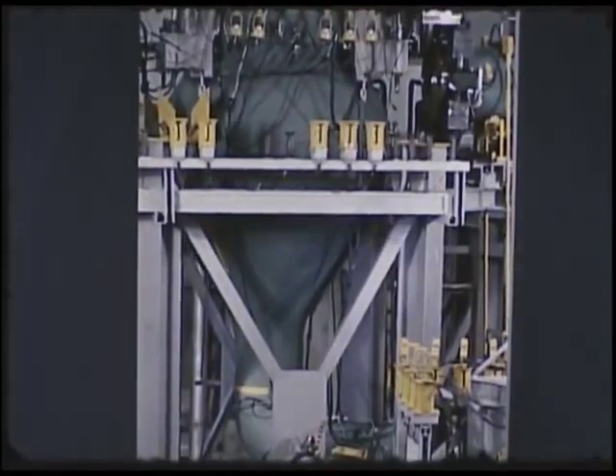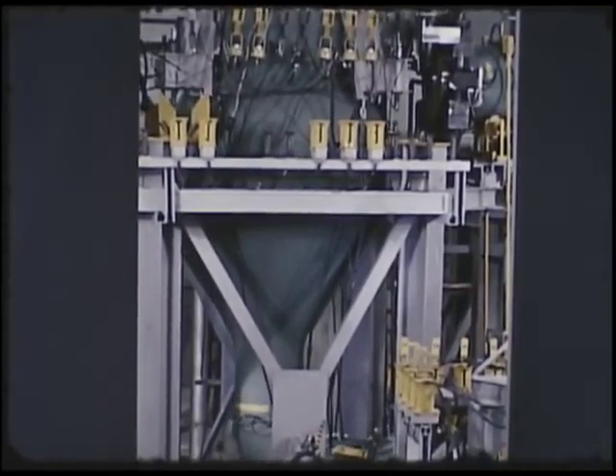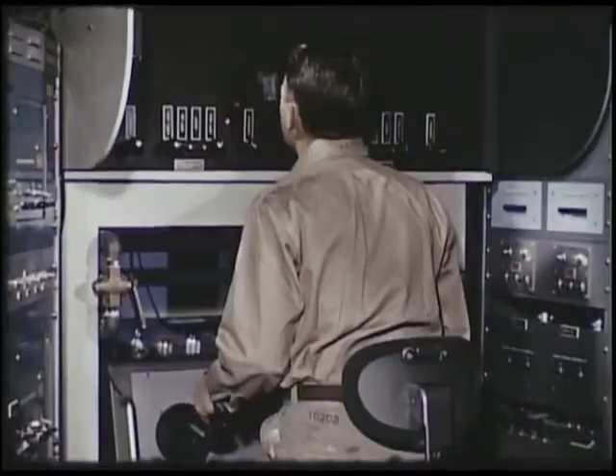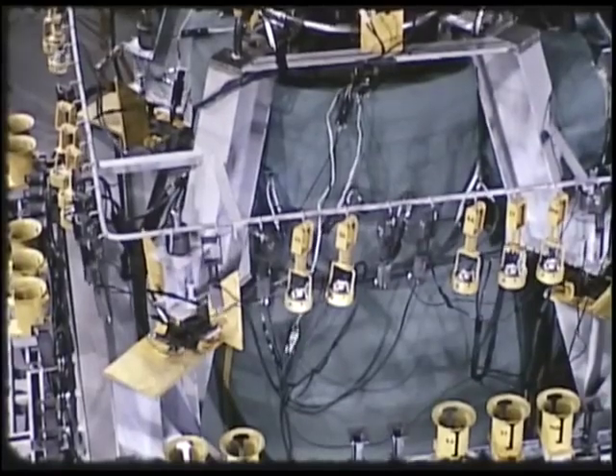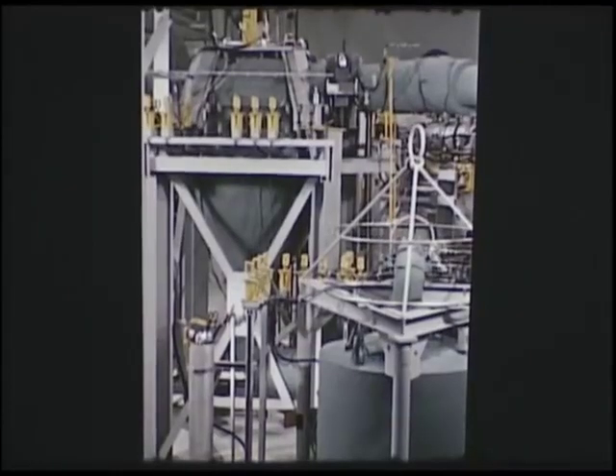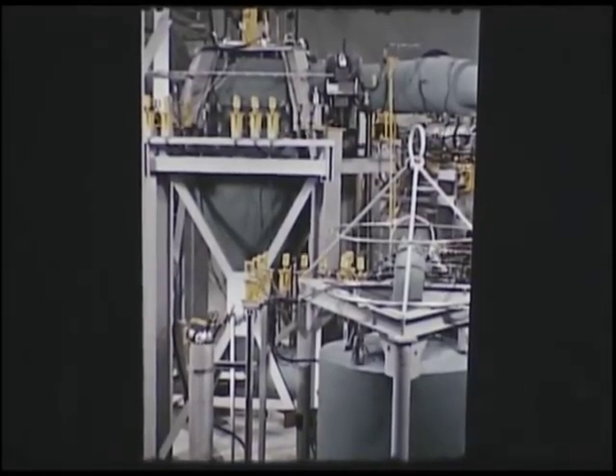Installation of a new or repaired reactor, pump, and motor is essentially the reverse of the removal of these components. Occasionally, it is necessary to use the manipulator to assist the crane in positioning the reactor during installation. This operation, like the others, requires experience, care, and patience. Total time for removing and installing the reactor less pump is 24 hours.